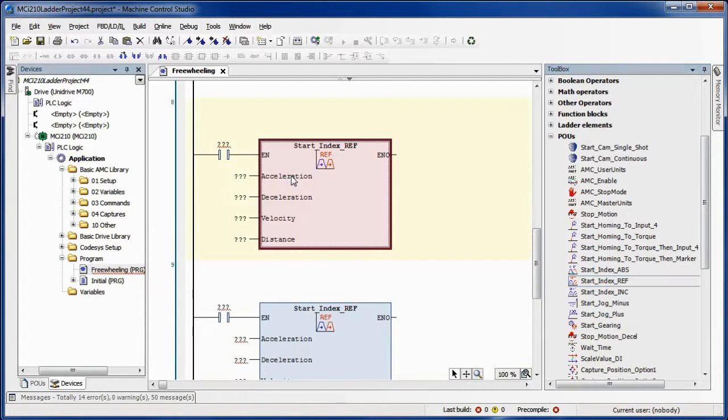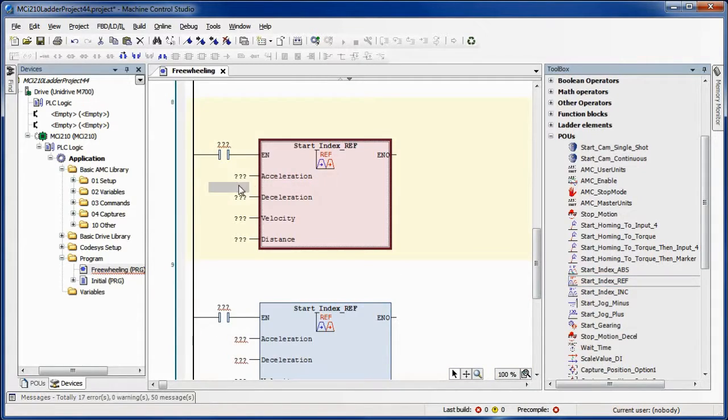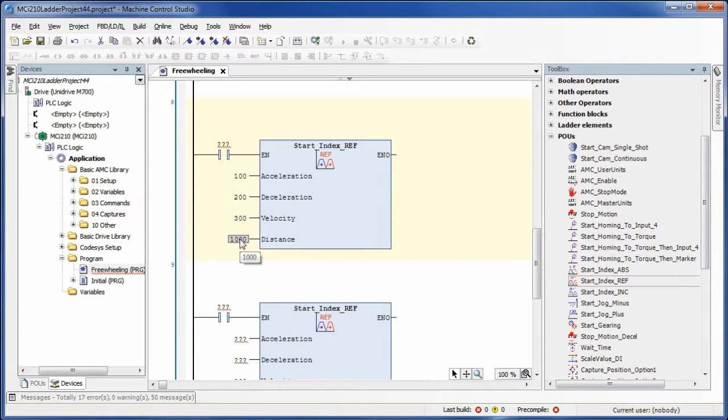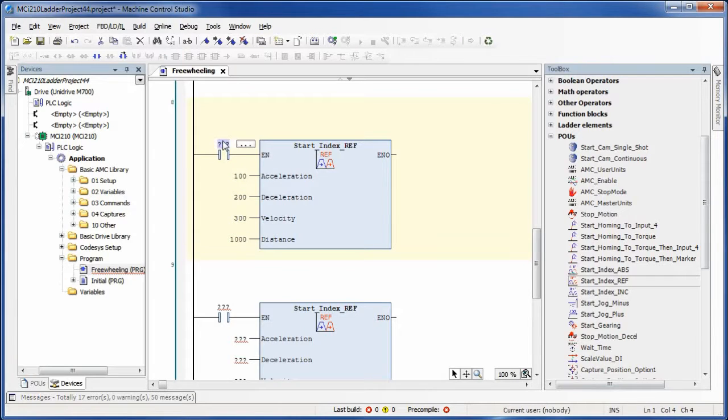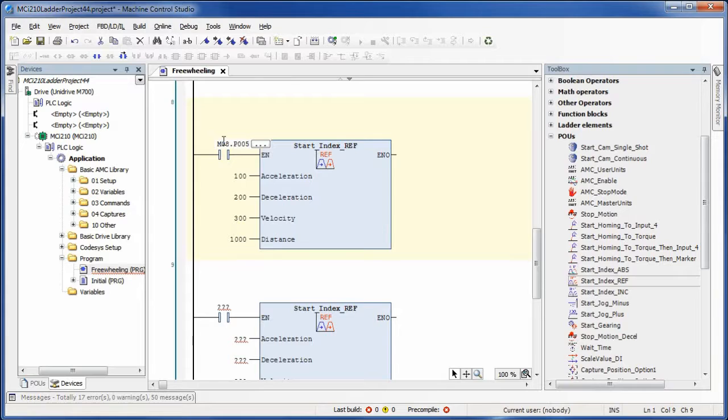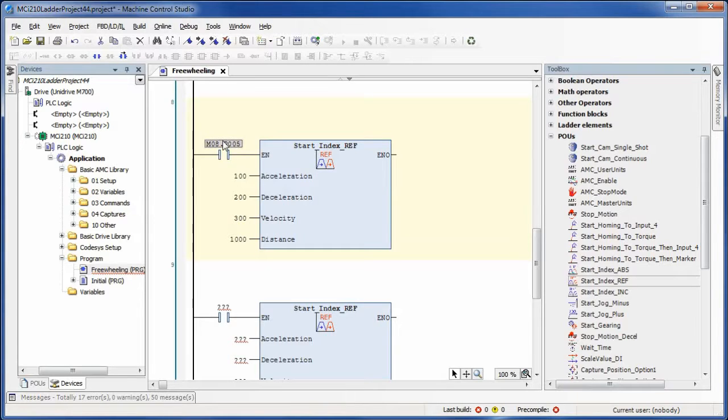Now we are just simply going to populate the input data to each of the blocks. For this drive menu 8 is the digital inputs. Parameter 5 represents input 5 and parameter 6 represents input 6.